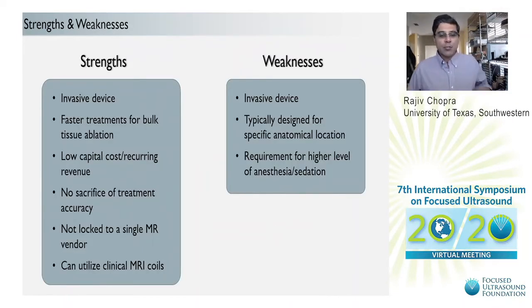So, the strengths of using minimally invasive devices for MRI-guided focused ultrasound. Well, first, I would say a strength is that it's an invasive device. And what I mean by that is that by putting a device inside the body, you eliminate many of the challenges experienced with externally located devices, such as near-field heating and acoustic windows. Many times by putting the device right into the region or close to the region we want to treat, those issues are no longer an issue. We've also observed in my research and others' that having the device located inside the target region, for the reasons I mentioned just now, leads to faster treatments for bulk tissue ablation. So one can ablate, coagulate or heat many cc's of tissue per minute, and that does lead to faster treatment times. And that's also been observed, by the way, with lasers and other less complex devices that are not focused ultrasound.